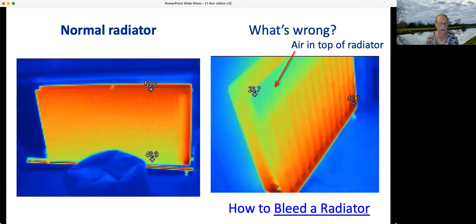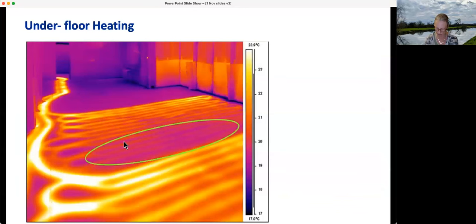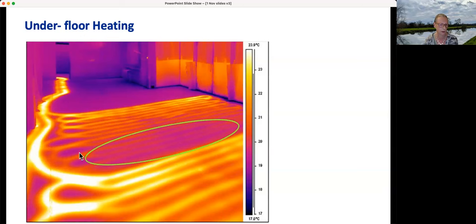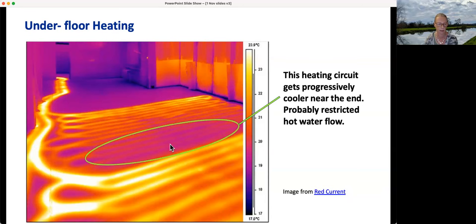Interestingly, fixing the air in your radiator will not actually reduce your heating demand — in fact it might even increase it — but it will mean you'll actually get warm, and there are advantages to that. If you've got underfloor heating, it's an absolute nightmare trying to find what's wrong with it unless you use an infrared camera. Here you can see parts of the floor are not heating up, probably due to some restriction in the hot water flow, and you don't have to dig up the floor to check.